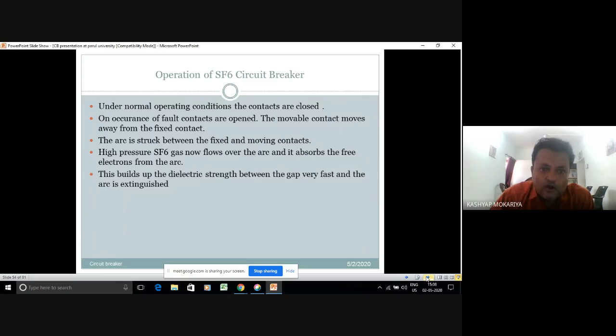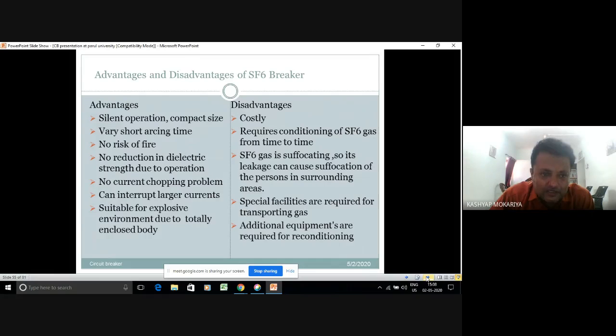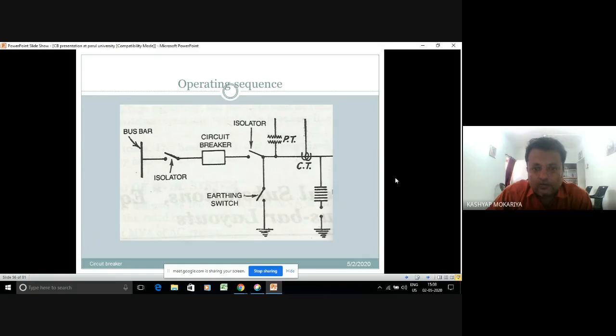So under normal condition the contacts are closed. On the occurrence of the fault, the contacts open at the zero point. The SF6 flows over the arc and creates the negative ions, and rapid dielectric strength is built up and the arc is extinguished. Silent operation, compact size, very short arcing time, no risk of fire. Disadvantage, costly, requires conditioning of SF6 gas. Some other issues we have to deal with. Now this is a very important slide to me.